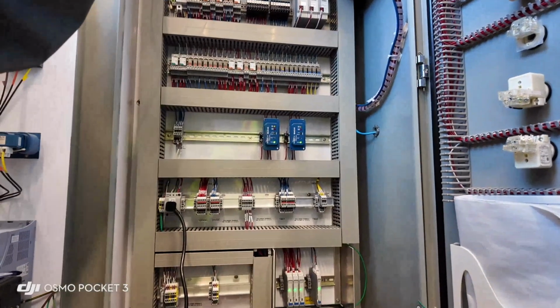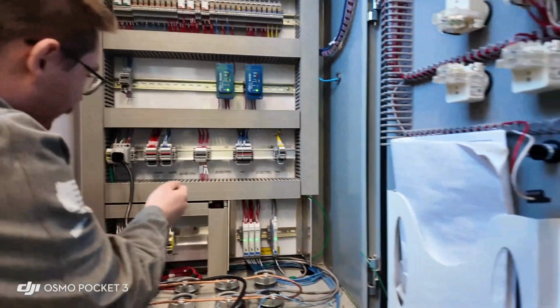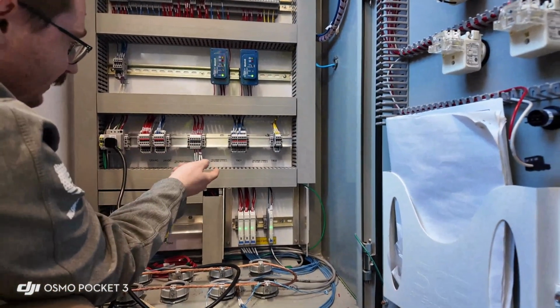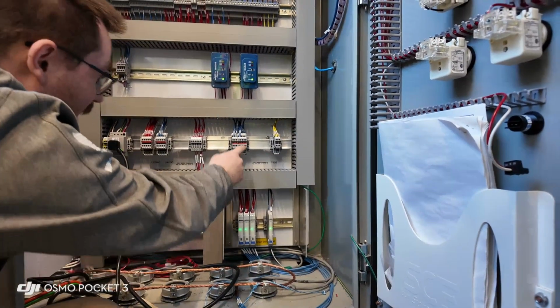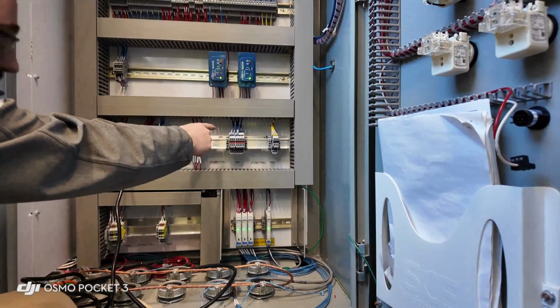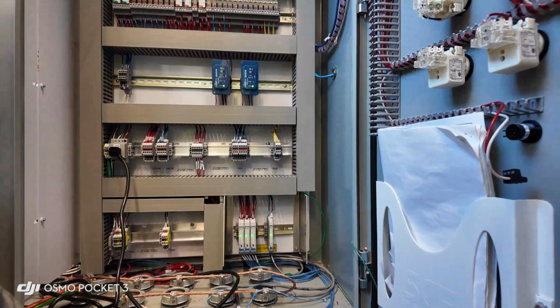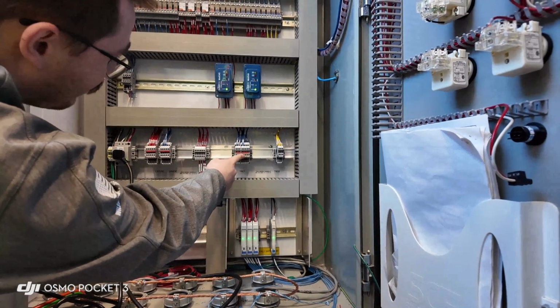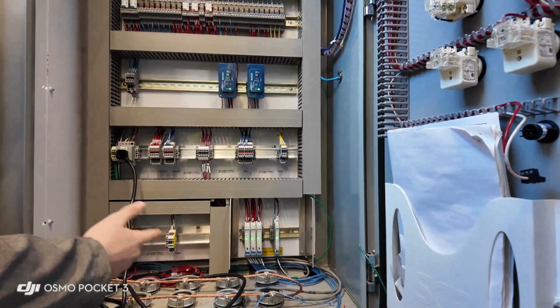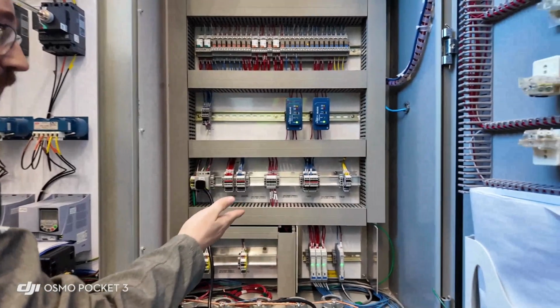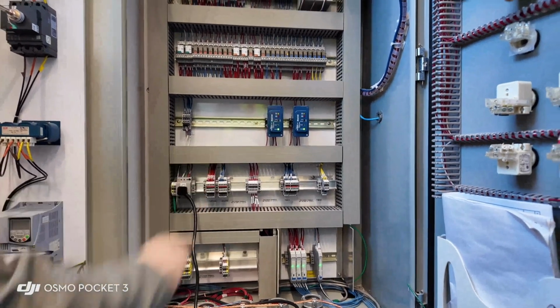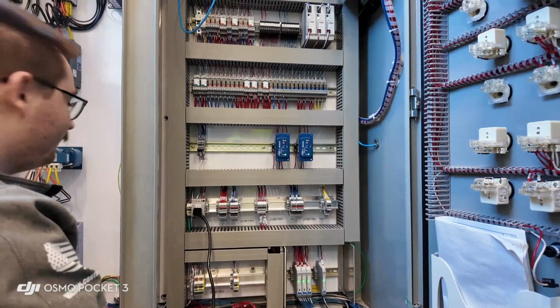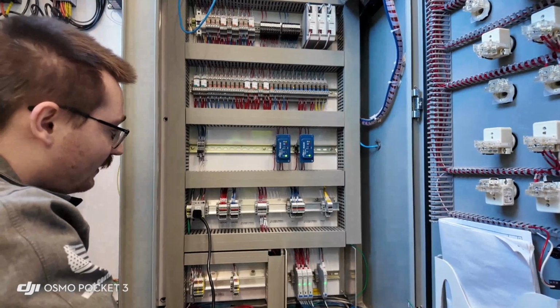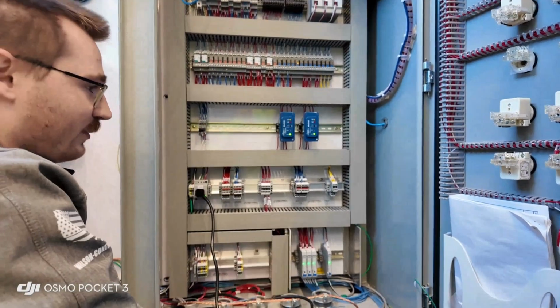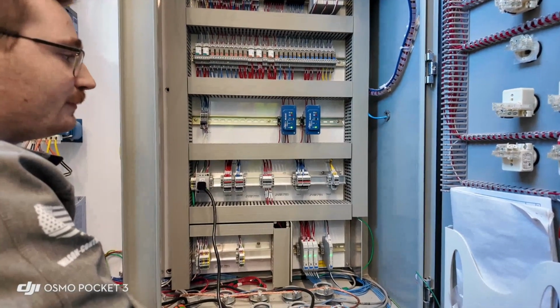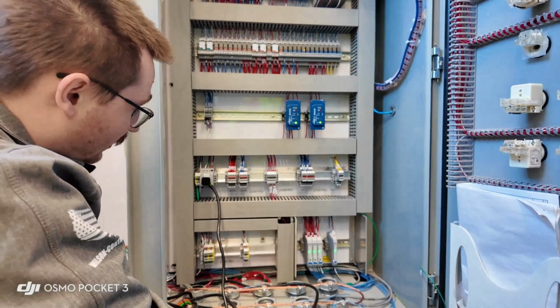These are just field wiring terminal blocks. So this is just power equipment outside the panel. This is TB1. TBD1 is your digital inputs. Most of these are spare, but a few of them are for a future pump 3. We gave you terminal blocks, so it's quick and easy. You can just wire right to the terminal blocks for anything you need to monitor, exactly like these ones. And then we provided you 25% spares on all digital and analog terminal blocks.